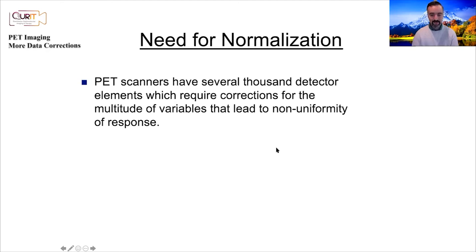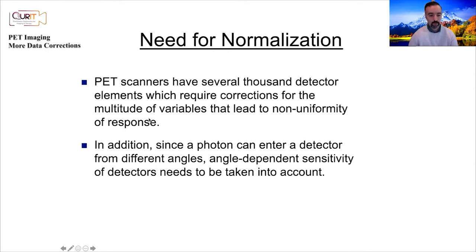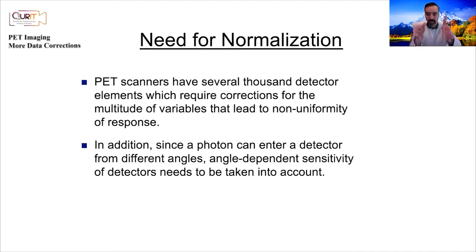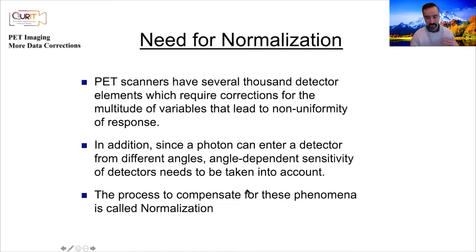PET scanners have several thousand detectors — say 10,000 to 20,000 — and so we should regard corrections that can lead to non-uniformity issues. Since a photon can enter a detector from different angles, especially in PET because there's no collimator, you're coming from many different angles and the cross-section changes. There's angle-dependent sensitivity of the detector, so you really have to correct for these before reconstruction.